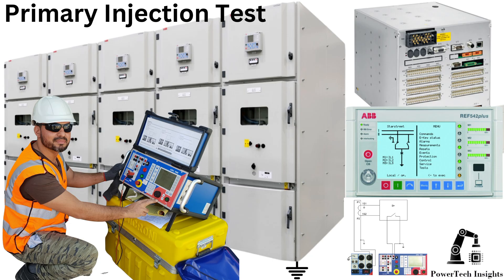The primary injection test ensures that the REF542plus relay, current transformers, wiring, and circuit breaker trip mechanism function correctly under fault conditions. This guide provides a detailed step-by-step procedure for conducting the test using an Omicron CPC100 and the HMI screen of REF542plus.